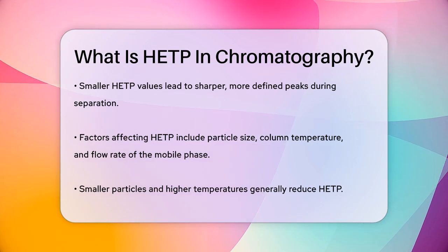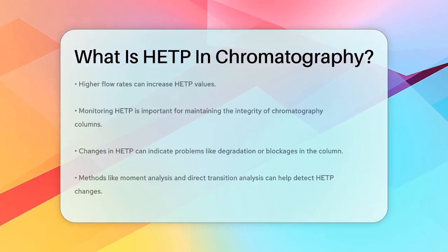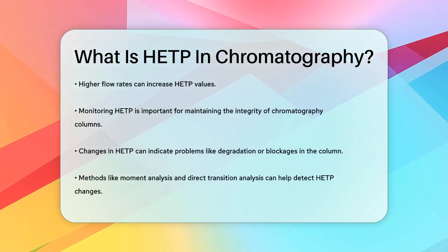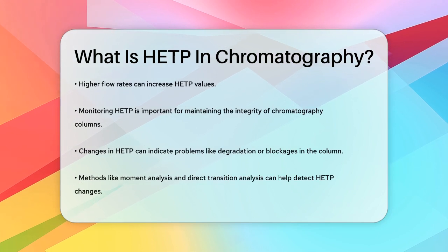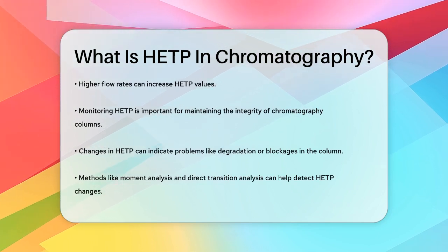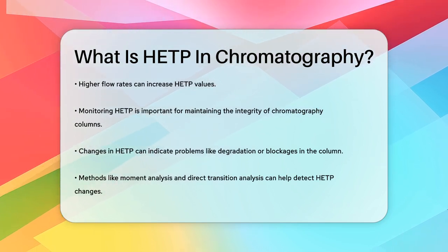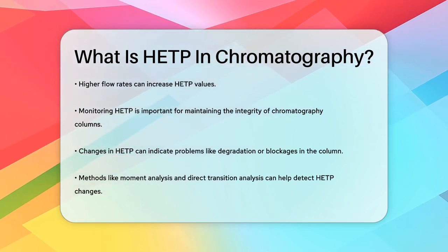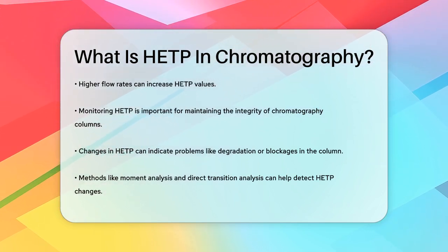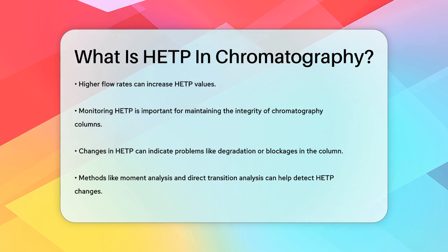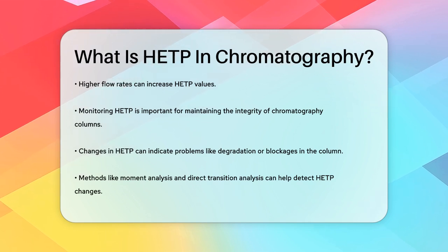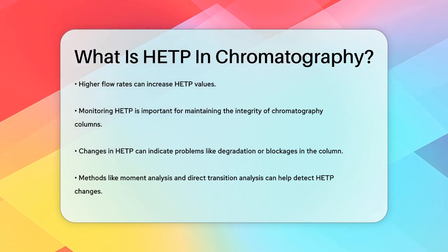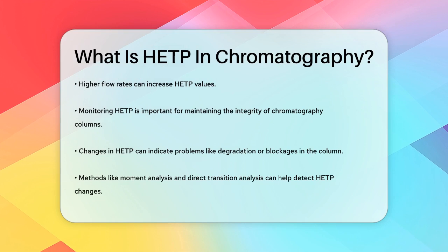In practical terms, monitoring HETP is crucial for maintaining column integrity. Changes in HETP values can signal issues with the column, such as degradation or blockages, which can be detected through methods like moment analysis and direct transition analysis.